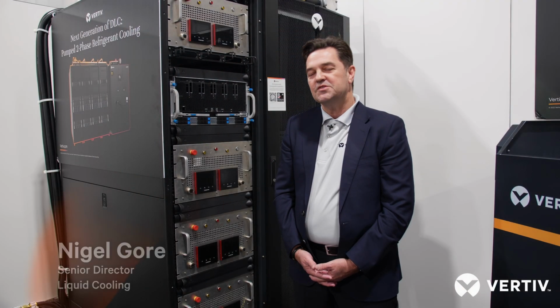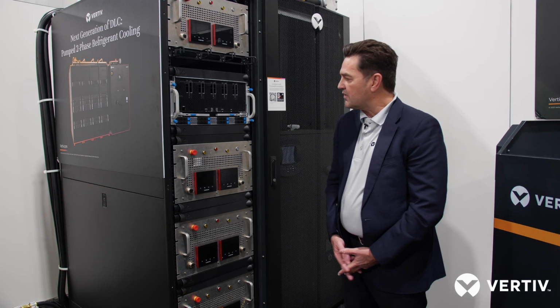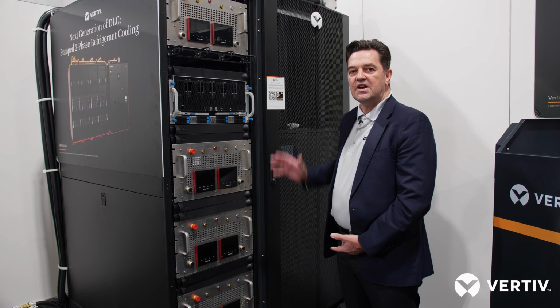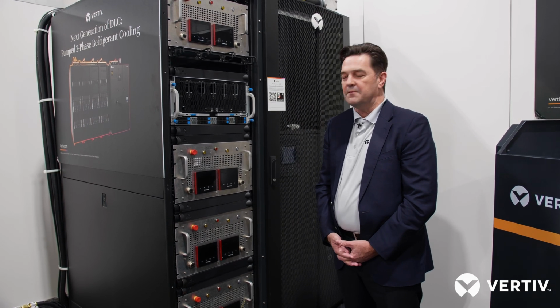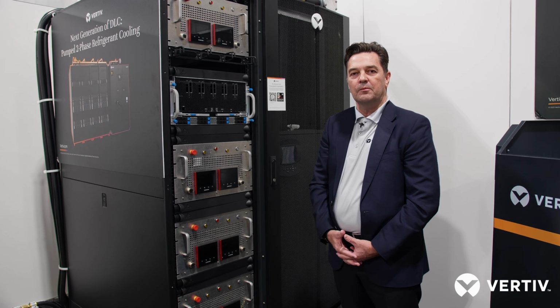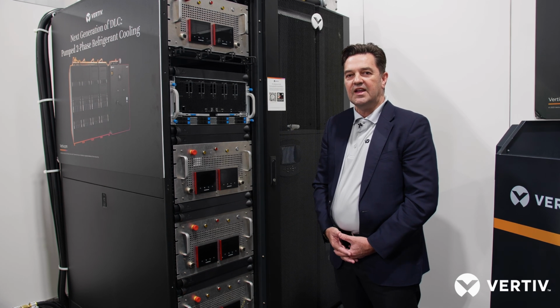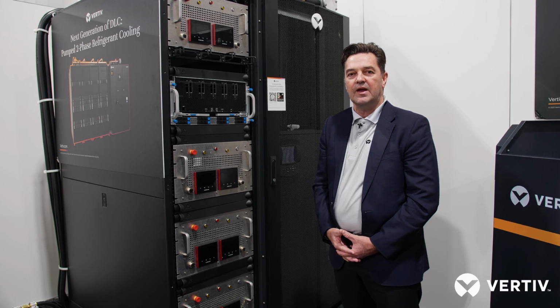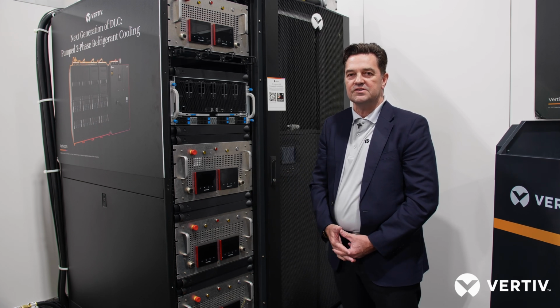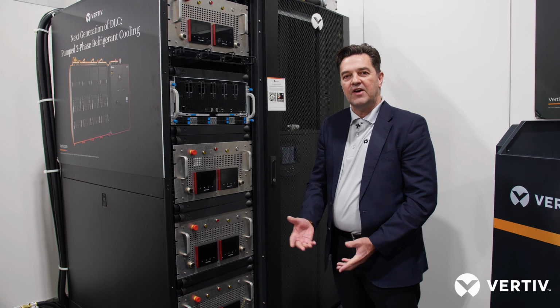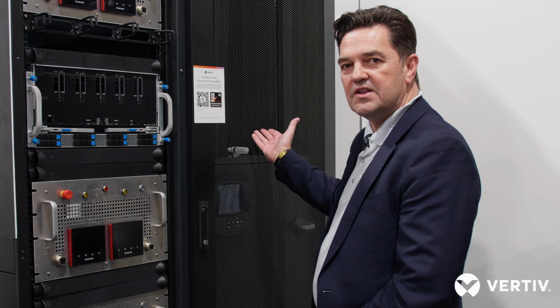The system that we have here, I'm just going to describe it very quickly, is essentially an air-assisted refrigerant liquid cooling system. We have here on the main side a condenser and refrigerant repository that then pumps the refrigerant in a liquid form through to the server rack, and we're able to then hit the servers, and they have evaporators on them as they're processing and firing on those processes. The refrigerant will heat up, it'll vaporize, and therefore the cooling effect will happen. The vapor of the refrigerant will then return back to the system through a condenser coil, which is cooled through a fan-assisted system, which is resident in the data center facility, to then return back into a liquid state for the process to then reoccur.